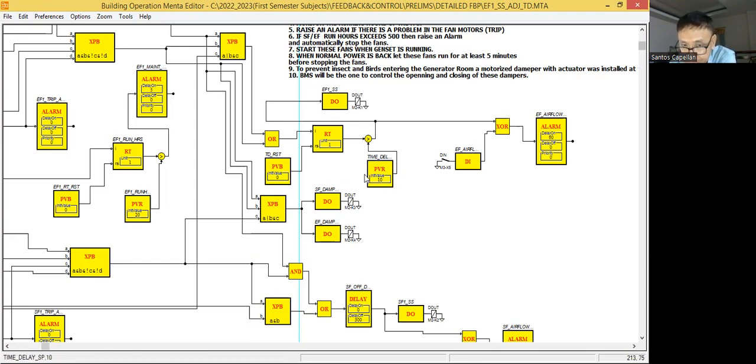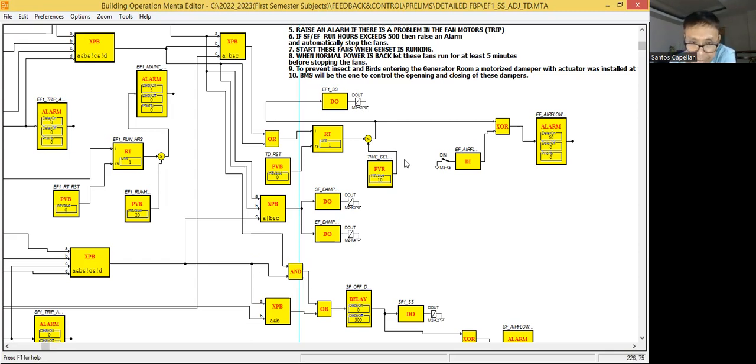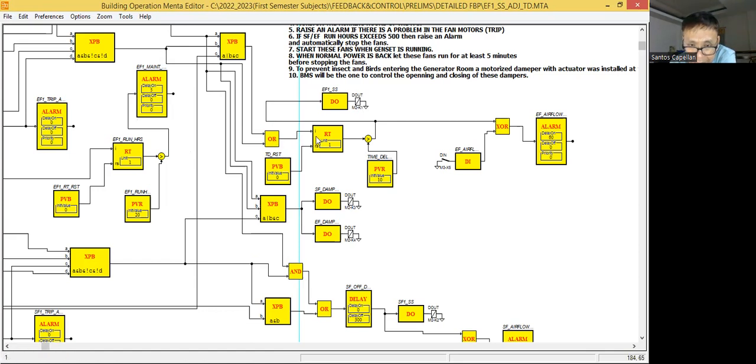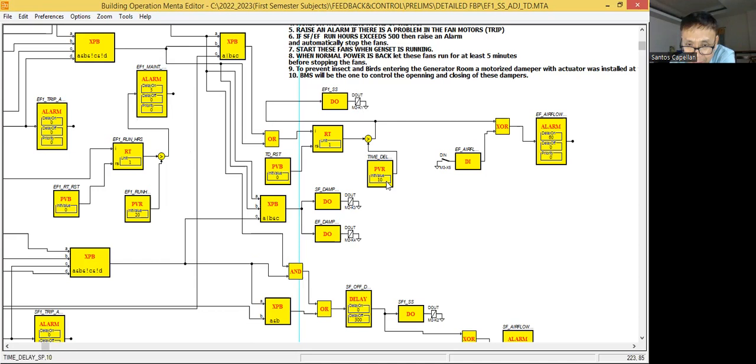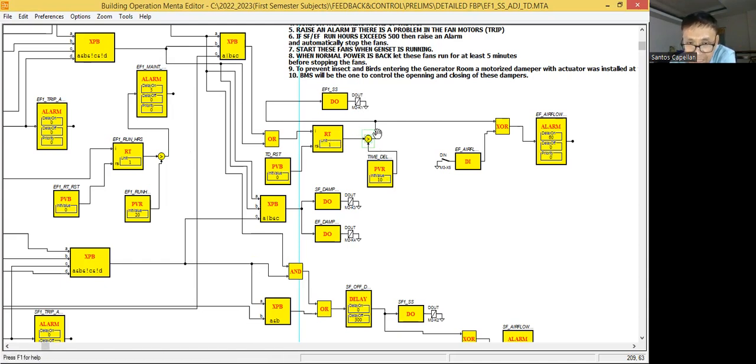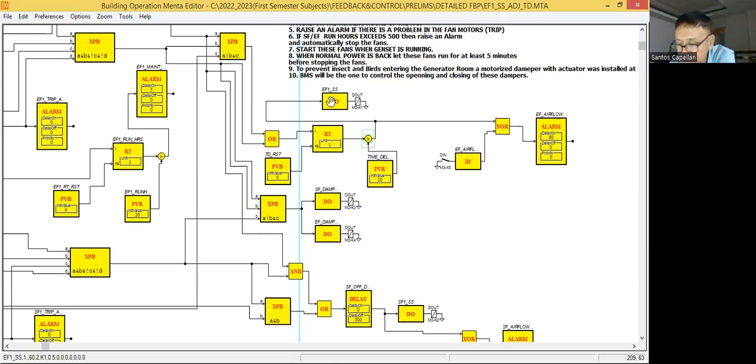In the graphics they need to bind the graphic point or graphic object for this point. When everything is okay to start, this will become one and start the counter. The counter will count, and because I'm using an operator greater than, when the output of this runtime is greater than this, then that's the only time it will start the equipment.